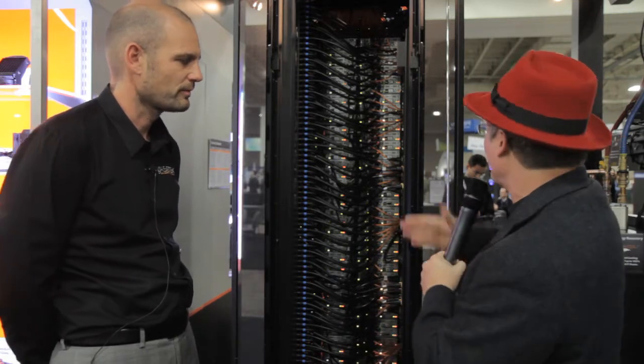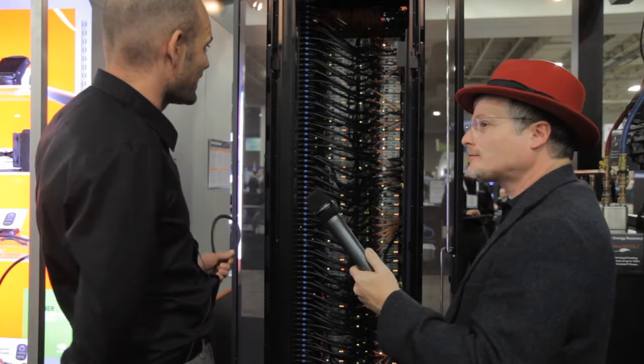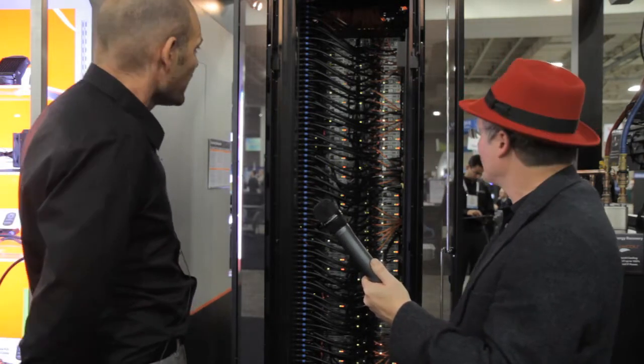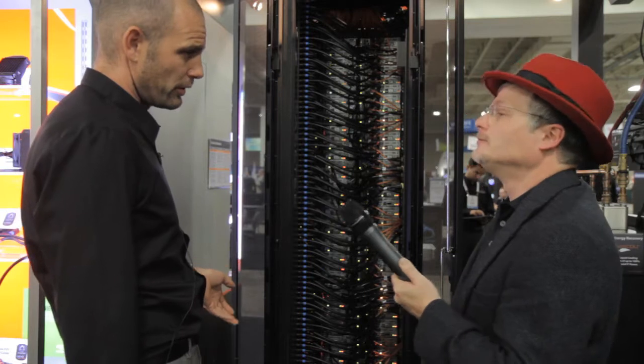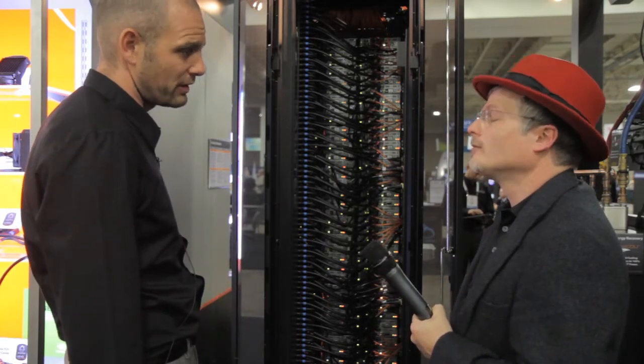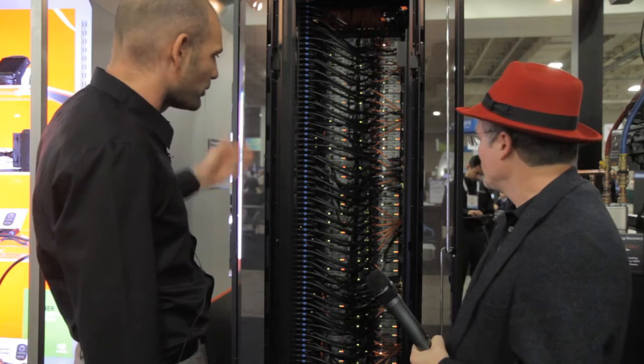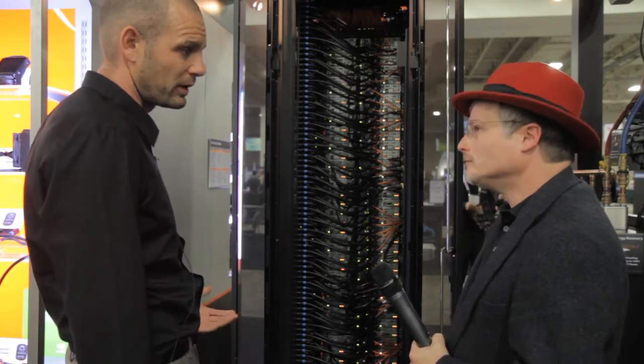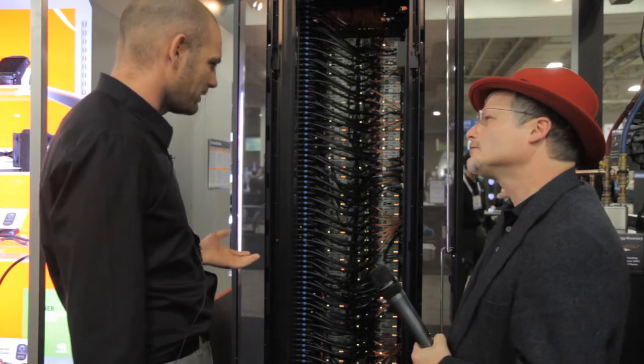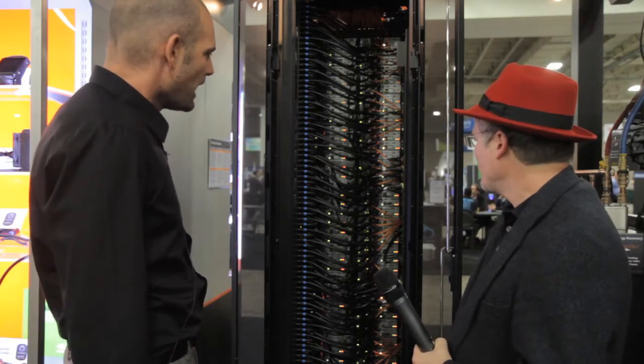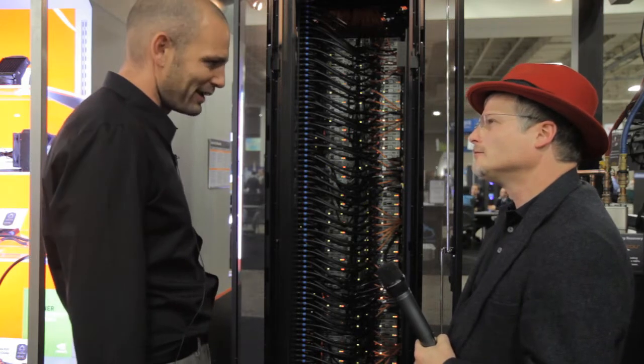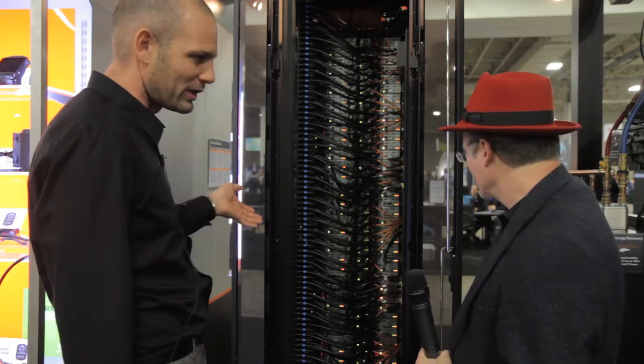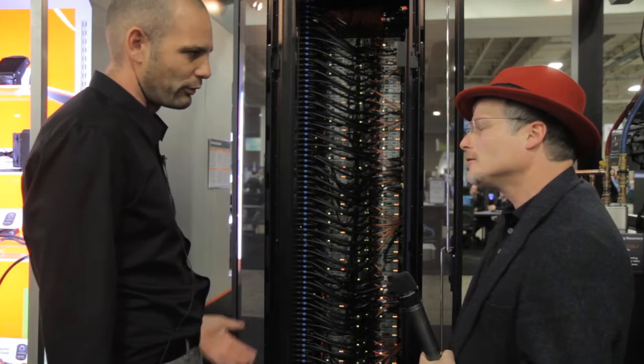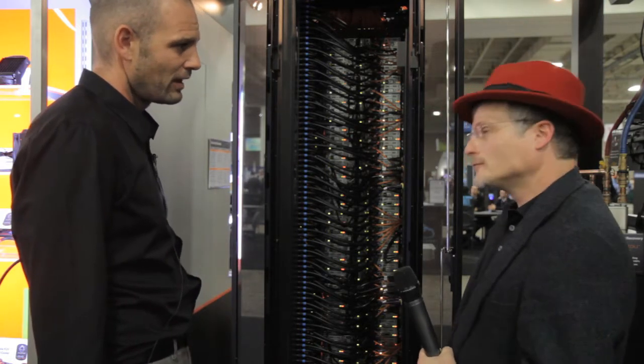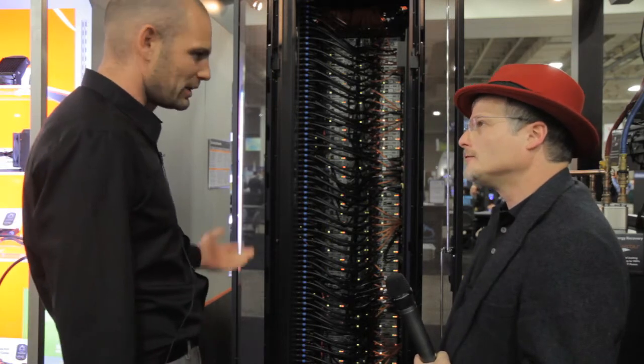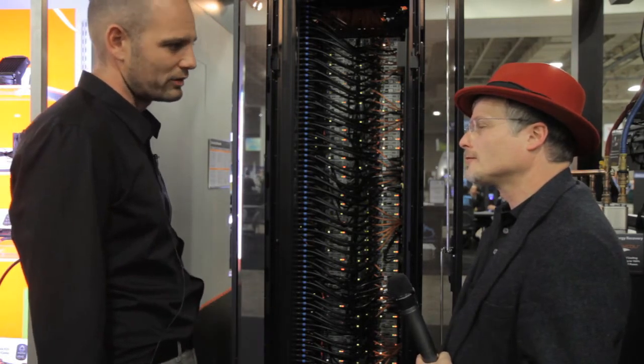What are we looking at here, André? We got a full rack, a bigger size than normal, a 48U rack with 92 nodes and 235 watt processors in each, adding up to 40 kilowatts of power. It's probably the most dense and powerful rack you can buy today. The unusual thing is that although we put in 40 kilowatts of power, we spend something like 300 watts cooling it. In a normal data center, out of 40 kilowatts you'd add another 15 kilowatts just for cooling alone.